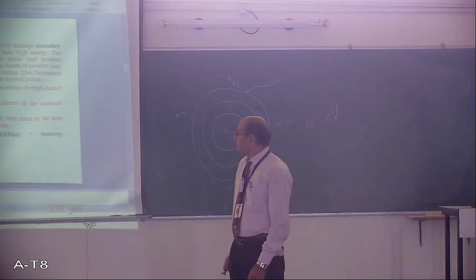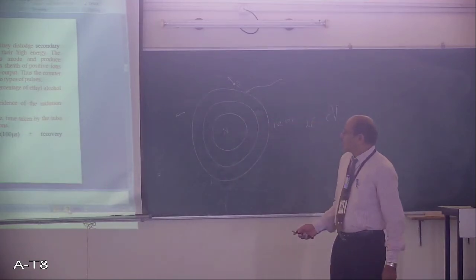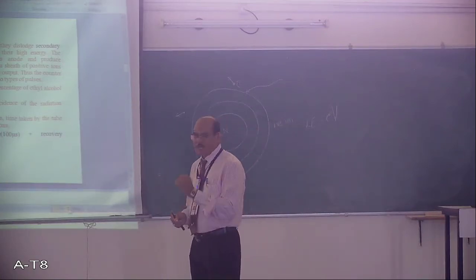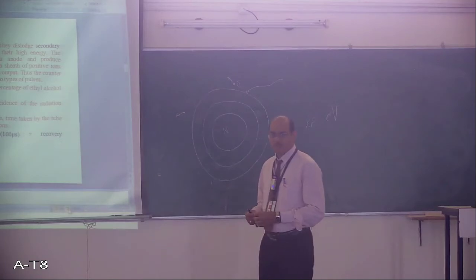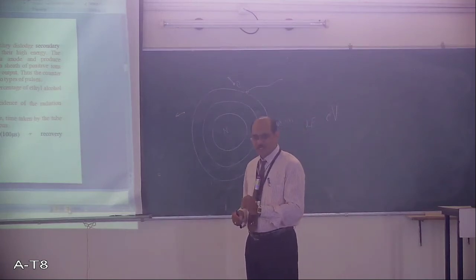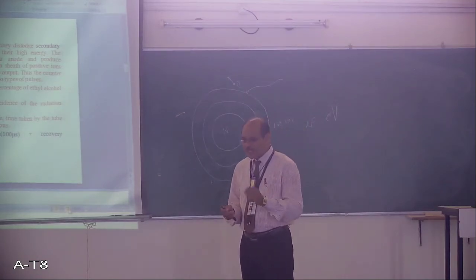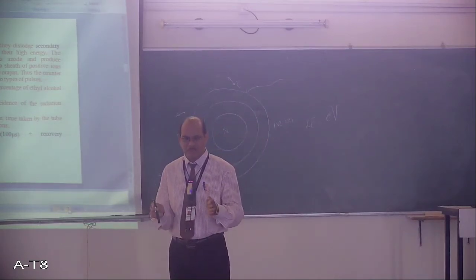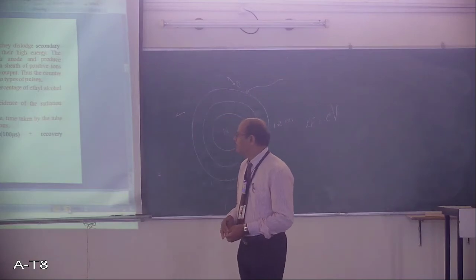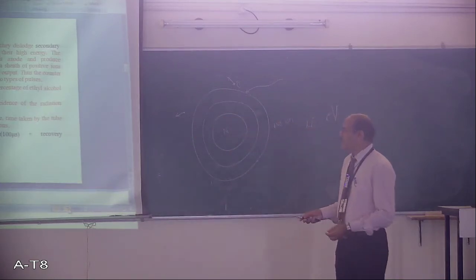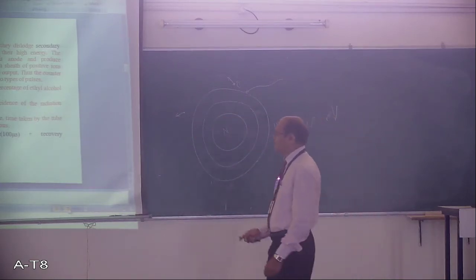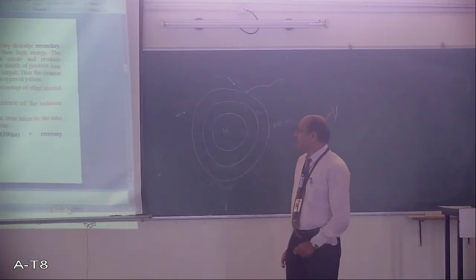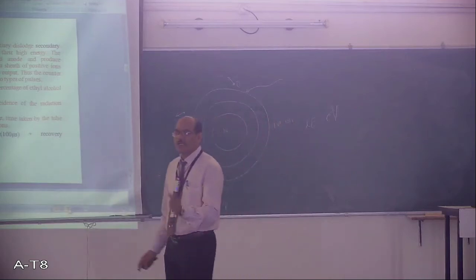Now, in the process, when a pulse is obtained, the pulse lasts for some duration. After one pulse, until the second pulse is obtained, there is a certain time gap. That time gap is accounted for by the dead time and the recovery time. So what is dead time? Dead time is the time during which the incidence of a radiation particle will not be registered.